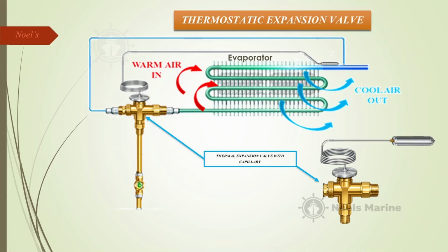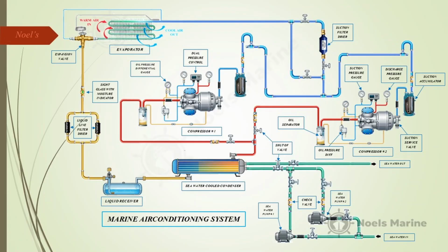And what happens when this high-pressure liquid actually squeezes through that tiny valve? An immediate, massive drop in pressure. And as we know, a drop in pressure equals a drop in temperature. So it instantly becomes a freezing cold mixture. Yes, it becomes a very cold mixture of liquid and what we call flash gas. And that cold mixture is sprayed right back into the evaporator, ready to start the whole loop over again. That is the closed-loop refrigeration cycle. It just goes round and round.